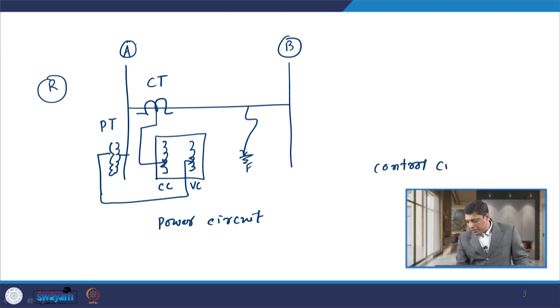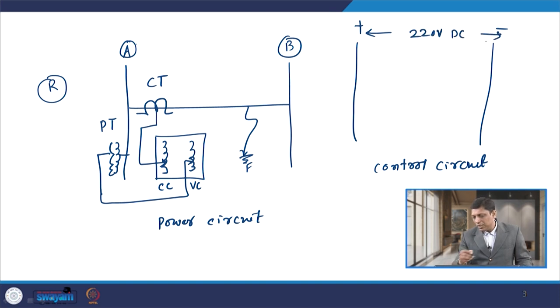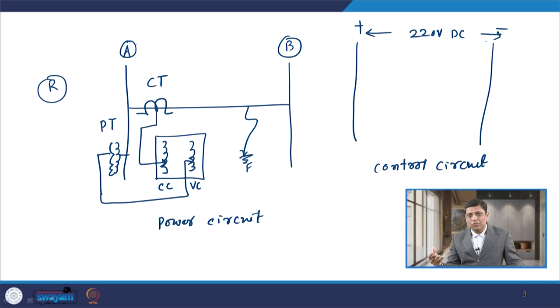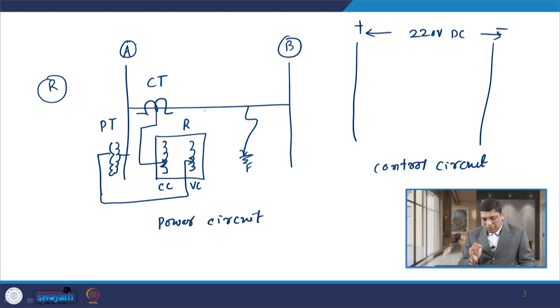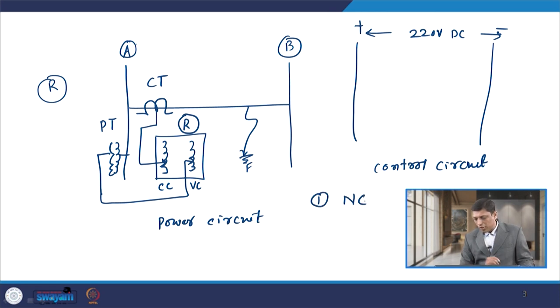The other circuit the relay has is the control circuit. In the control circuit, all the contacts of the relay are connected. The control circuit requires 220 volt DC supply — sometimes 110 volt DC supply — and nowadays you can also give AC supply. If the relay is connected in the power circuit, it has certain contacts. Basically there are two types of contacts: one is known as normally closed contact and the other is known as normally open contact.